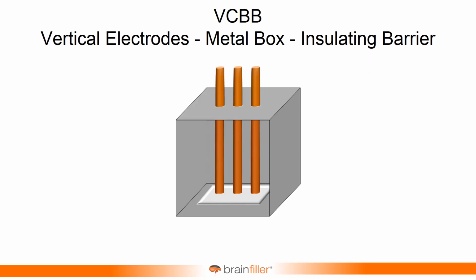And my diagram, like this, it just shows, this is actually more what the IEEE 1584 test was based on, what they did. And I say they because it was actually the project team that did this. It wasn't the working group. So what the project team did is they took the 3 metal rods and they put the barrier down at the bottom of the box. And so you got the same kind of thing. You have the initial arc starting, and then the energy would hit the bottom and be ejected a little bit, come out with a little more authority. That's how we'll refer to it. And so that was the VCBB, as we call it.